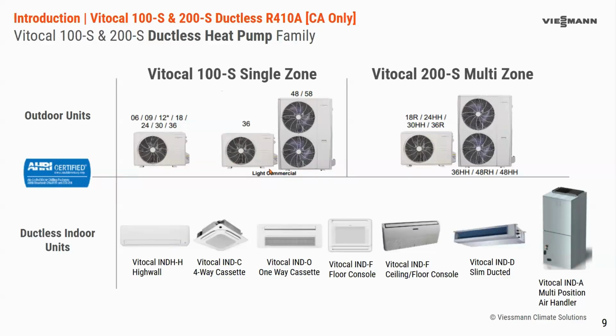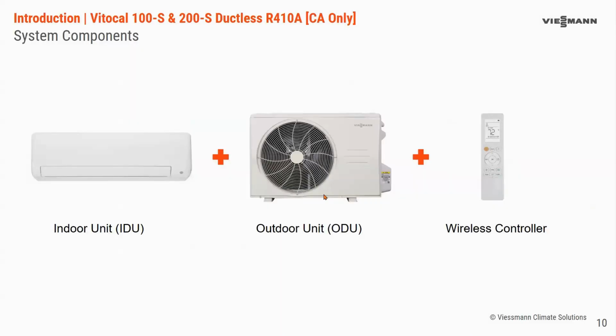The only caveat when selecting your equipment is to note that the light commercial outdoor units have specific light commercial indoor units due to the separate communication wire on those larger sizes. Again, when you're selecting equipment and looking at your product data and your installation manual or resources, just ensure that if you are selecting a light commercial single zone, you do have a compatible indoor unit. So as I mentioned, the three main components in the system are the indoor unit, outdoor unit, and a controller. All of the indoor units come with a wireless controller. Some indoor units also come with a wired controller, and the wired controller is optional for all units.